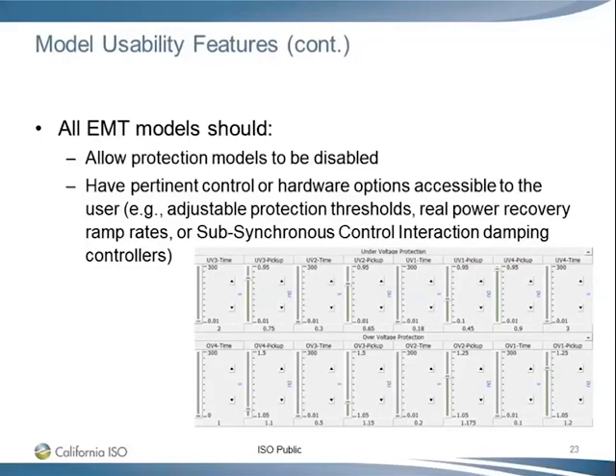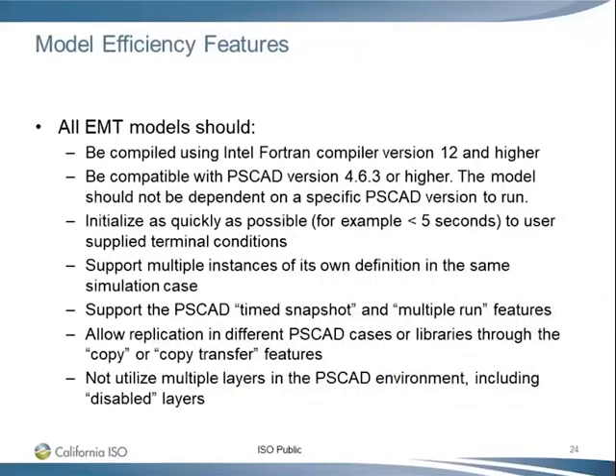Okay, so also we require that you show all the protection models, and we need a way to enable and disable each protection. The other control options, like if you do have some other control, such as a subsynchronous control interaction controller, then we should have a way to disable that. Next slide. Okay, one more question in the chat. They asked, are there any EMT testing standards to adhere to? No, there is no EMT model standard so far. All the standards are for the positive sequence.